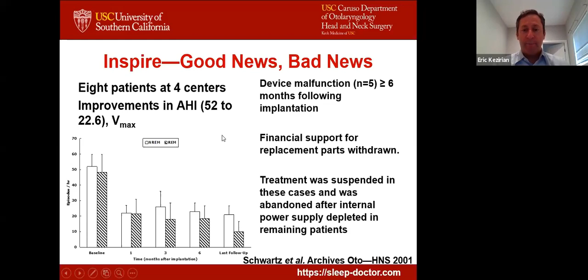The problem was the devices broke down. Six months or more after implantation, 5 of the 8 devices broke, and one of the pitfalls was related to the leads, not so much the device. But with more learning, we found that the electrode design, putting almost a semicircle coverage, the half cuff electrode, was probably not the way to go. Medtronic was like, yeah, it's interesting, but they withdrew support for the program and replacement parts. So treatment was suspended in cases where the devices broke, and then abandoned after the remaining patients had the battery, the power supply, run out. So it was largely abandoned.